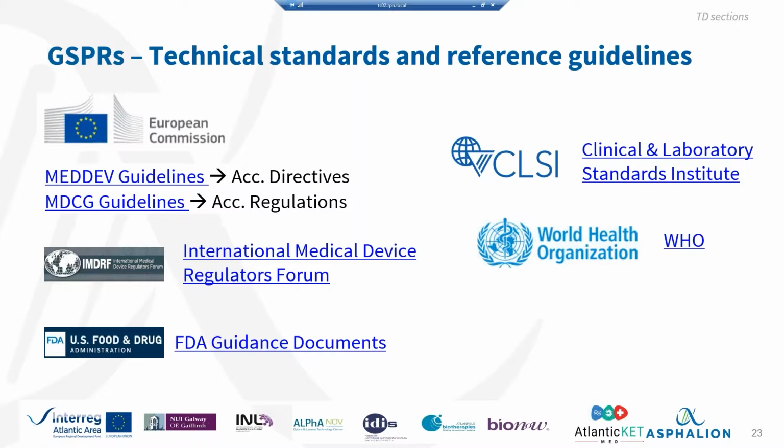Besides the technical standards, there are also plenty of guidance documents. Okay, the most common here in Europe are MEDDEV and MDCG. MEDDEV was guidance according to the directives, while MDCG guidelines are according to the regulations. So with the time, it should be moving towards MDCG. Up until now, you can still use MEDDEV, but with time, you should go switching to MDCG. Okay. Besides that, we've got the International Medical Device Regulators Forum, which publishes guidance on several topics, but not just for Europe, but also for other countries.